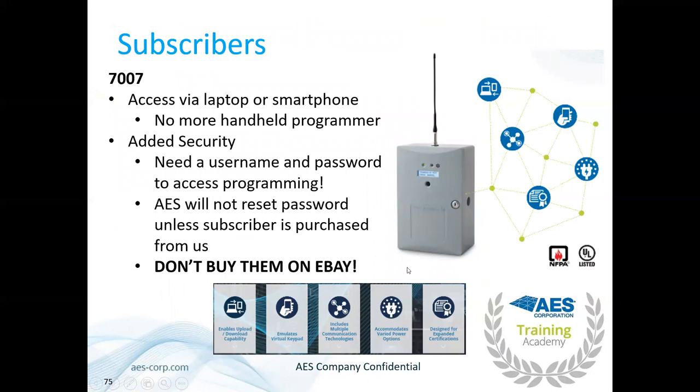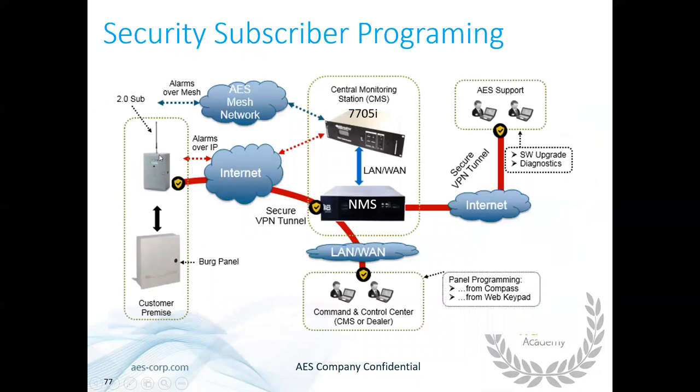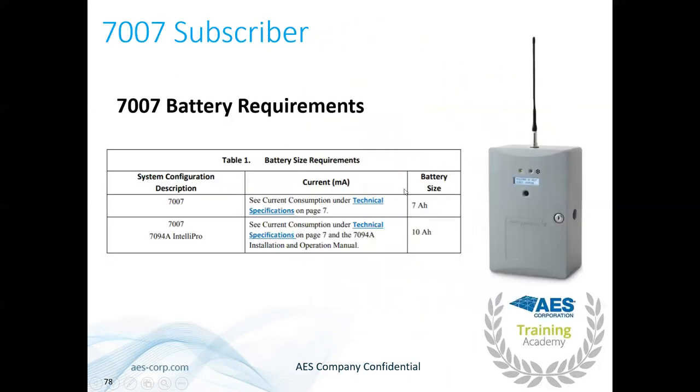The 7007 is our Burg or Residential Fire subscriber. No handheld programmer — requires a username and password. Don't buy on eBay. Upload and download via the Honeywell Compass 2 platform, requiring our NMS — this is for remote panel programming and virtual keypad emulation for technicians, not end-user interactive services. Remote programming works via the alarm mesh: the 7007 reaches out over the mesh, talks to the receiver, the receiver talks to the NMS, and the NMS opens a secure VPN tunnel to the subscriber. The 7007 requires a 7 amp hour battery when not using the IntelliPro.